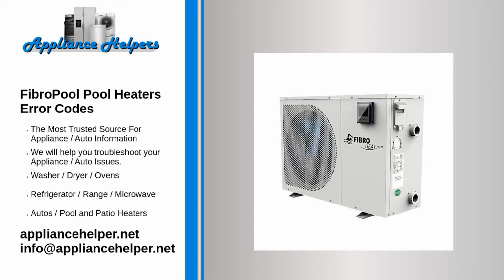Code EE1. Problem: high pressure protection. Code EE2. Problem: low pressure protection. Code EE3. Problem: flow failures. Code EE4. Problem: phase sequence protection. Code EE5. Problem: in and out of the water temperature difference is too large. Code EE8. Problem: communication failure.